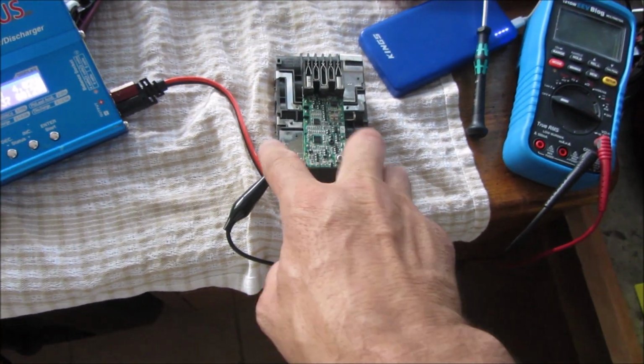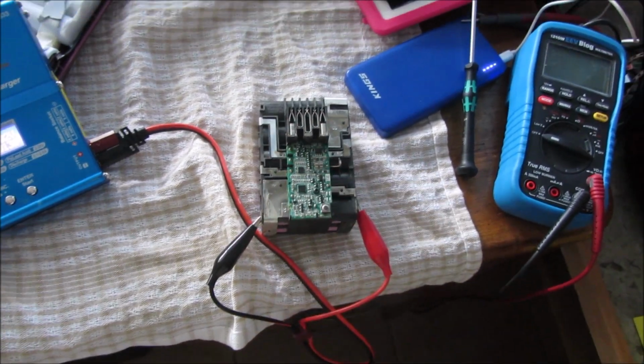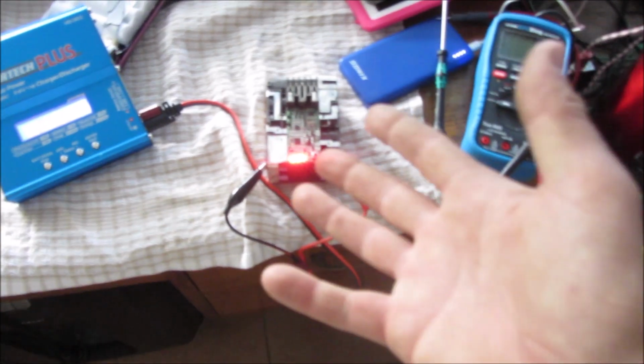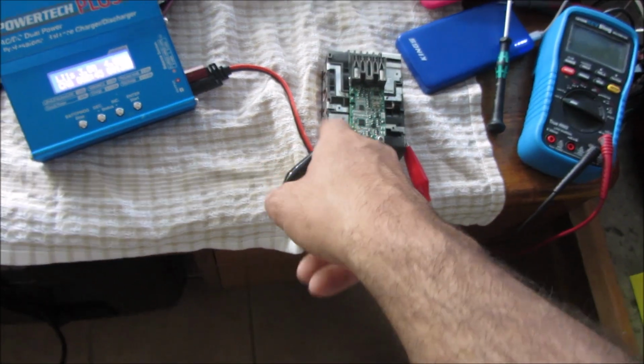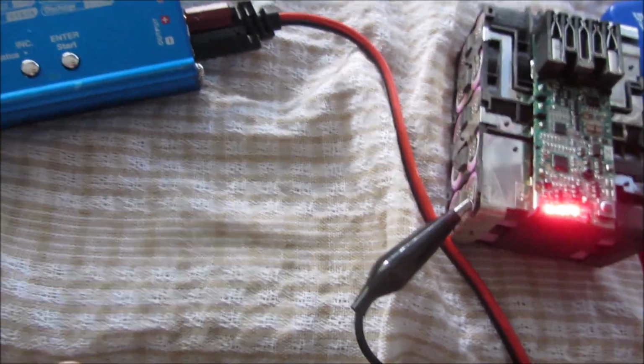So this will read 3.24 volts, and they're just out of balance. Then the BMS says no to the charger, because the BMS picks the highest or lowest rated battery cell. Since there's a fully charged cell in there, it tells it not to charge, and the charger goes into what's like a police car mode, meaning it's an emergency. If it tries to charge it, the cells could go into thermal runaway and catch fire. But doing it this way, I'm monitoring the temperature of the cells, and they're not changing much over room temperature, which is good.